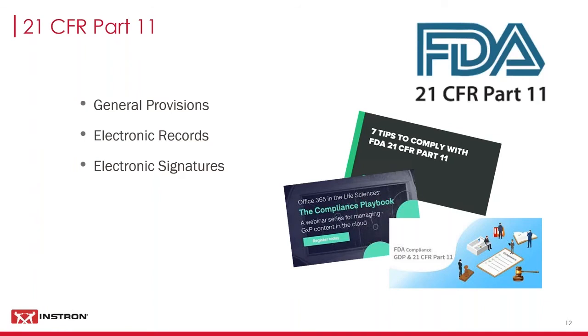An example that we see on the materials testing side in regard to this is the need for time-stamped audit trails when a user makes a change to a testing method, for example. It's part of the quality process. Usually an authority level has to be established for the user, and that would be defined in the system, and then they would be required to electronically sign any changes that they might make.